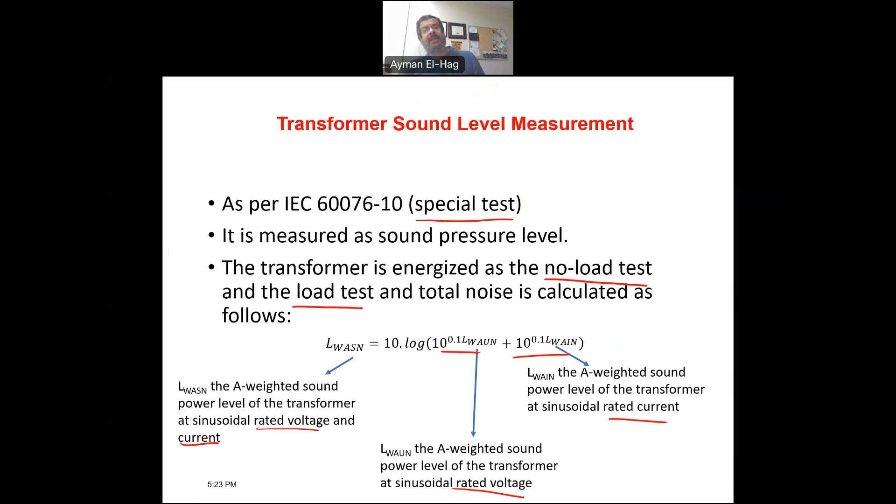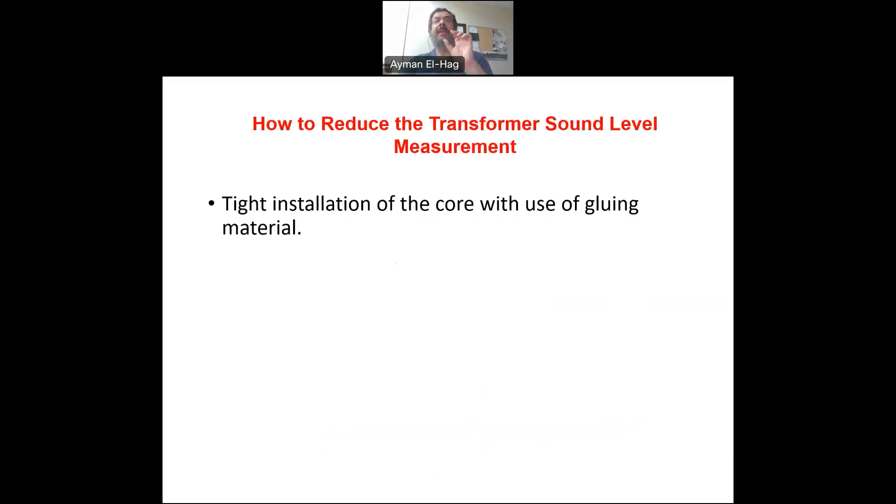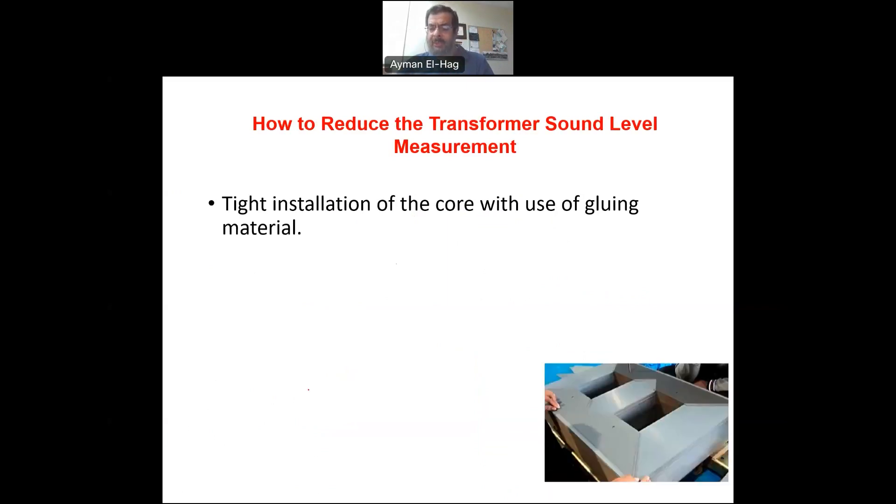The last question is can we reduce this sound or this noise coming from the transformer. There are a couple of techniques. I will just mention a few of them here. The most important one, because the core is a major contributor to the sound level, is trying to have a tight installation of the core. So there is no room for vibrations. So as we know the core is made from thin sheets to reduce the eddy current losses and then you have to install them manually.